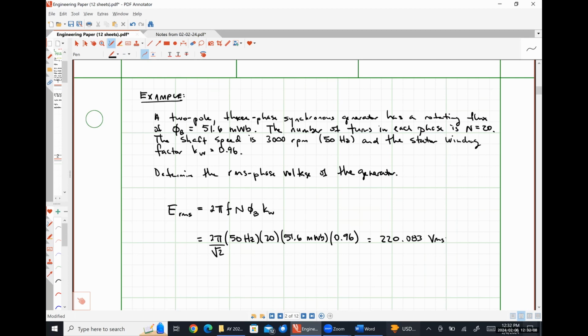What should the answer for the US voltage be? Something like that, but I'd just multiply this by 6/5 and call it a day, since that's the change in frequency — multiplying by 60 hertz and dividing by 50 hertz to convert from European to American. So it's just an easy scaling factor. Multiply this by 6/5 to get 264.099. So I'll put EU here, and down here 264.099 US at 60 hertz. This means if we used this in the States, we might want to back off the field current a smidge to bring that voltage down to the 240 we're used to.